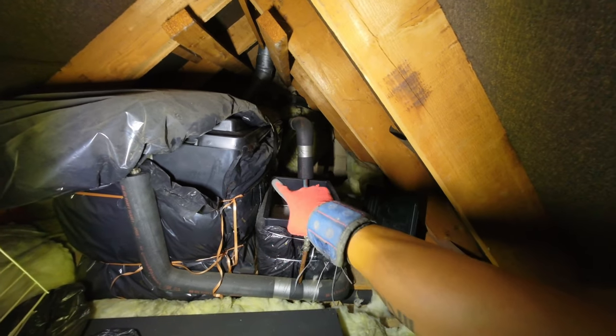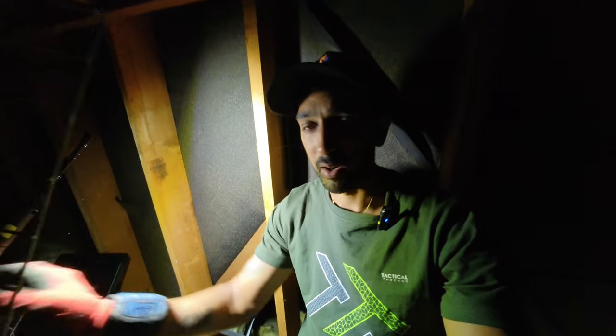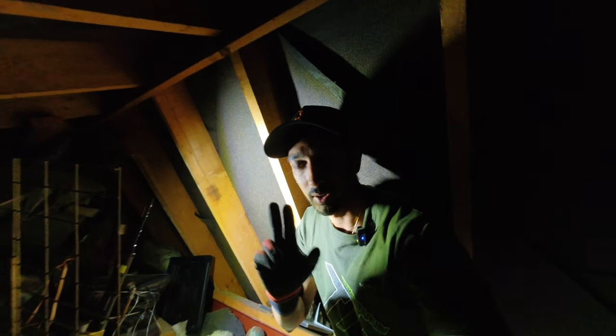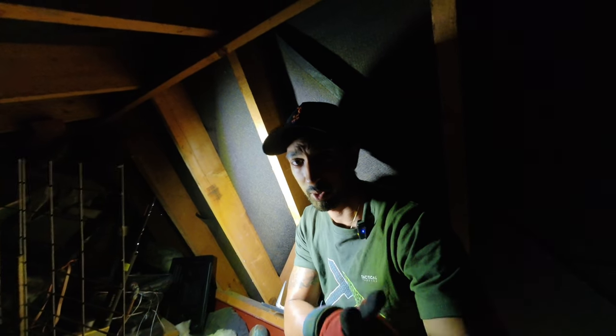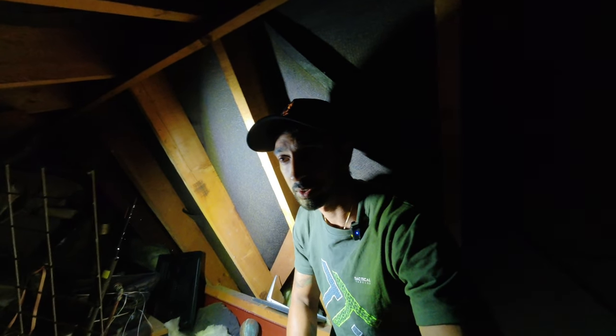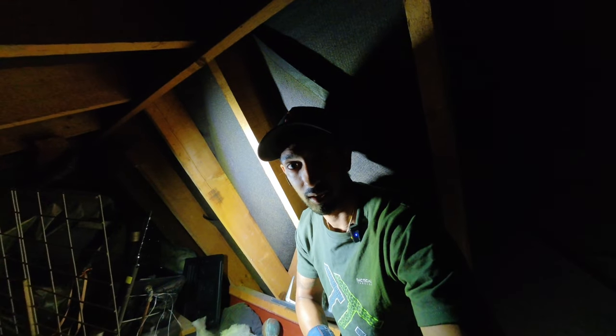We've got two outlets coming off the cold water storage tank — one feeding the cylinder, the other feeding the rest of the property. There is a loft room up here but we've confirmed there's no bathrooms up here, so I don't need to link it out up here. We can link it out in the airing cupboard. I'm going to leave those two 15mm pipes — the ones on the left — where they are, because I'm pretty sure those are heating pipes. We'll confirm it when we start taking the pipes up. In the meantime, we're going to turn the water off and start draining stuff down.